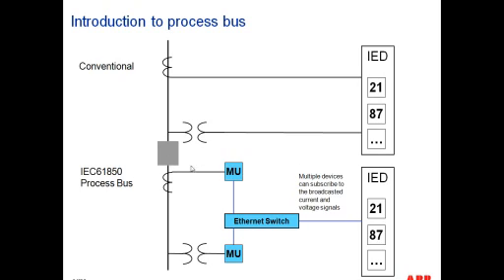When we talk about the IEC 61850 process bus, essentially what we have is, again, a current sensor and a voltage sensor, which may be conventional or non-conventional, but now we're introducing another device, which is what's called a merging unit. Essentially what that merging unit does is sample the currents and the voltages, and then publish those current and voltage samples via an Ethernet network. And now our relay, instead of obtaining the current and voltage information via copper wires, is obtaining that information in the form of digital messages over an Ethernet network.